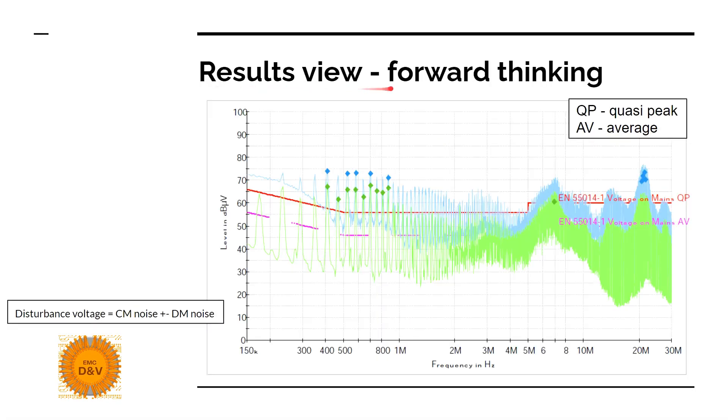Results view forward thinking. What you want to achieve is lower noise than the limits specified in the EMC standards for your device. Noise is measured in dBµV versus frequency and is usually from 150 kHz to 30 MHz. On the chart, you have two types of envelope for the peak detector and the average detector, which is usually used for narrowband emissions. The quasi-peak limits will always be higher than the average limits.